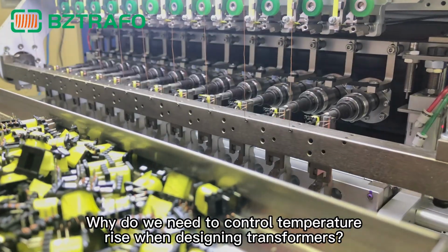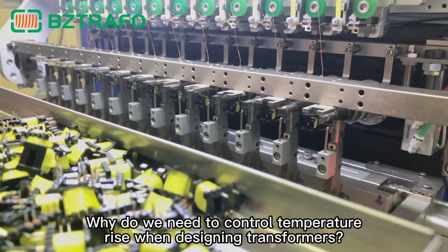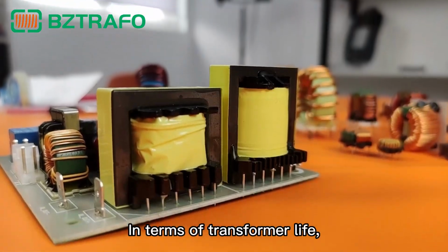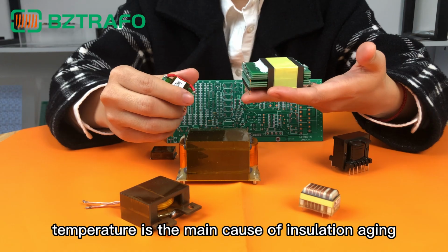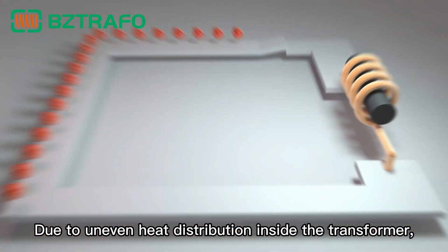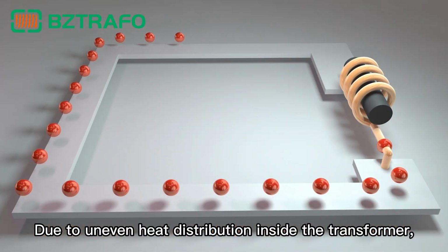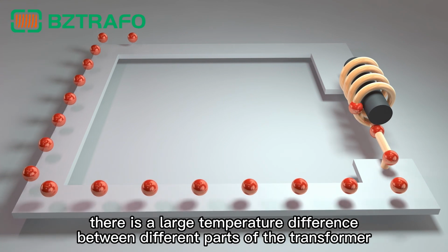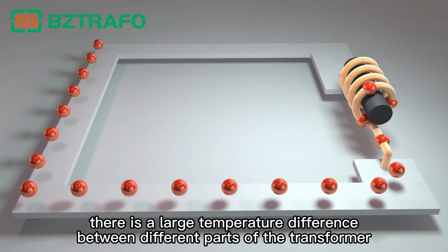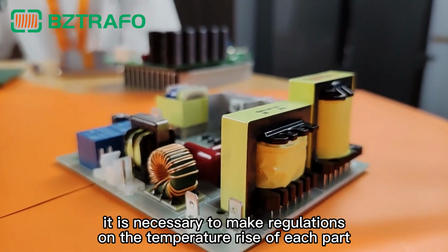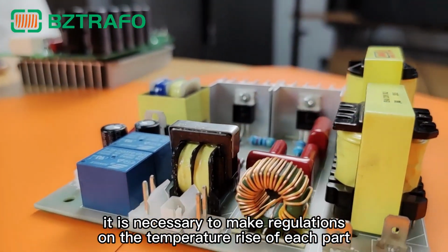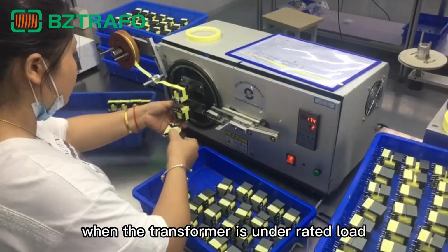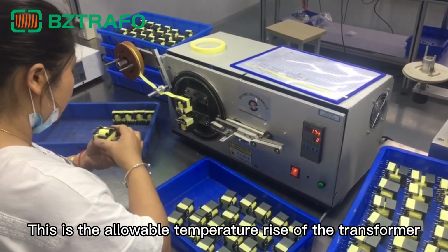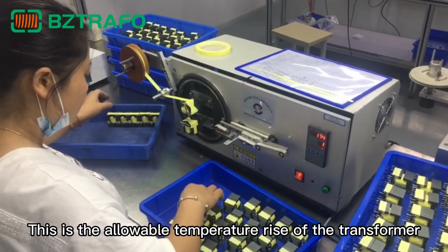Why do we need to control temperature rise when designing transformers? In terms of transformer life, temperature is the main cause of insulation aging. Due to uneven heat distribution inside the transformer, there is a large temperature difference between different parts of the transformer. Therefore, it is necessary to make regulations on the temperature rise of each part. When the transformer is under rated load, this is the allowable temperature rise of the transformer.